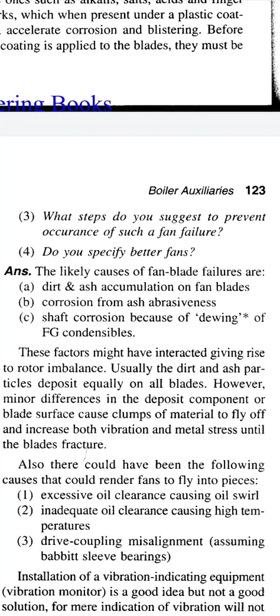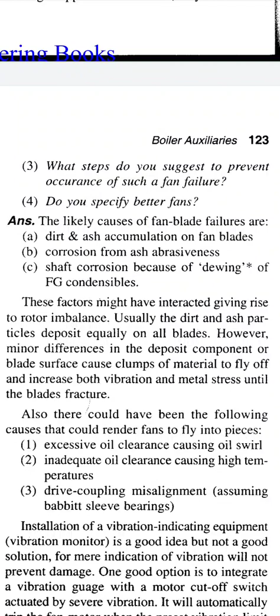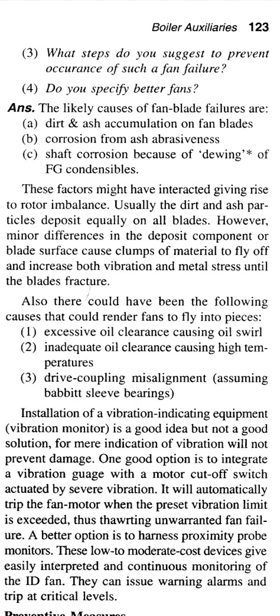Answer. The likely causes of fan blade failures are dirt and ash accumulation on fan blades, corrosion from ash abrasiveness, and shaft corrosion because of dewing of FG condensables. These factors might have interacted, giving rise to rotor imbalance. Usually, the dirt and ash particles deposit equally on all blades. However, a minor difference in deposition component or blade surface causes clumps of material to fly off and increase both vibration and metal stress until the blade fractures.